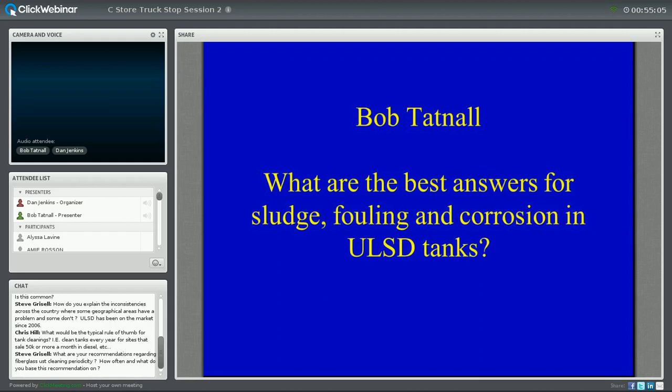So we went over and we stuck the tank. We stick them for water with a pole, of course. When we did it originally, arriving at that site, we got something between 1/8 and 1/4 of an inch of water in the bottom. Very low. After that transport had left, we went over and stuck the same tank, and we had over 3 inches of water in the bottom. So you tell me, can it happen a lot? Can it happen big time? Yes. I wish everything were perfect, but that water was delivered with the gasoline. What really hurts is it costs the same per gallon as the gasoline did.